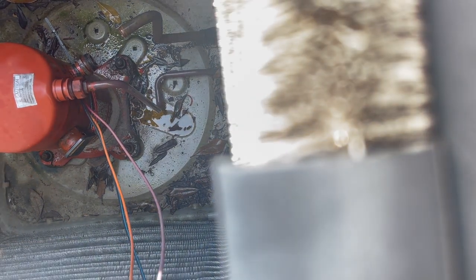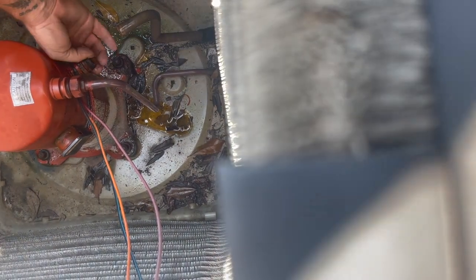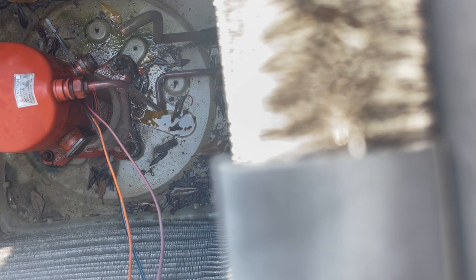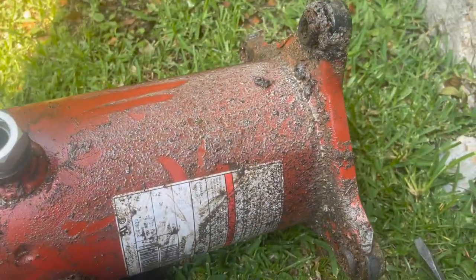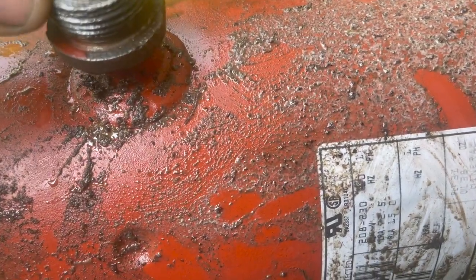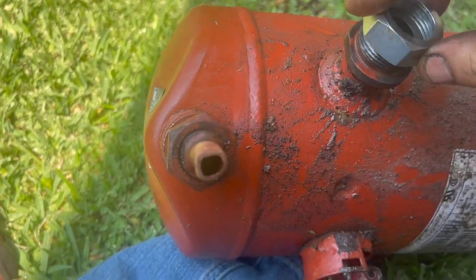It broke off, but I still think I can thread the new one on there - yeah, I think I can. I'm gonna clean up those threads with a wire brush and then try to screw the new one on. I had to pull the compressor out, had to chisel some of the old rotolock off the bottom, and I've hit it with a wire brush. Now we're gonna see if I can get this thing to thread. This is the new one.